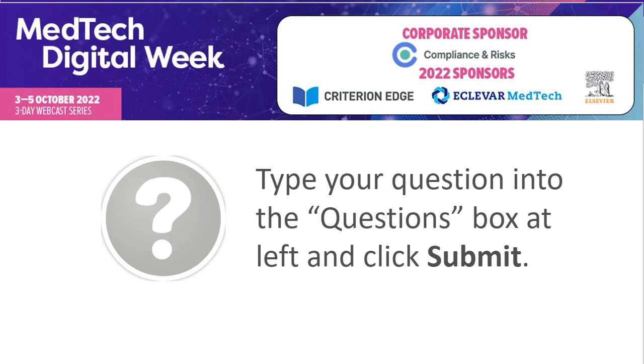Let's make this next one, Filippo, our last question. Sure. Must the safety and performance objectives have measurable acceptance criteria? The short answer to that is yes. Acceptance criteria, by definition, must be quantitative. Even if the answers are yes, no, they have to be measurable. I'll expand on my answer a bit, but that was a yes, no question, and the answer is yes, they do.